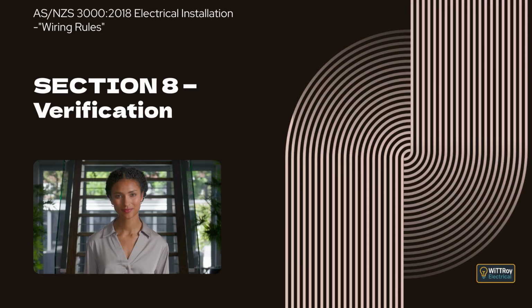Clause 8.3.5, Continuity of the earthing system. This clause explains that testing is required to prove continuity of the earthing system. This includes the main earthing conductor, protective earthing conductors, combined protective earthing and neutral conductors, and bonding conductors. The purpose is to ensure the earthing system is installed so that protective devices will operate if a fault occurs between live parts, other than the neutral, and the mass of earth. An effective earthing system prevents exposed conductive parts from reaching dangerous voltages under fault conditions.